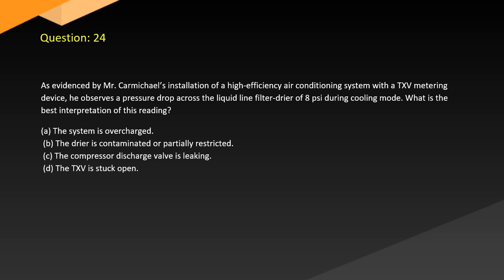Question 24. As evidenced by Mr. Carmichael's installation of a high-efficiency air conditioning system with a TXV metering device, he observes a pressure drop across the liquid line filter dryer of 8 psi during cooling mode. What is the best interpretation of this reading? A. The system is overcharged. B. The dryer is contaminated or partially restricted. C. The compressor discharge valve is leaking. D. The TXV is stuck open.